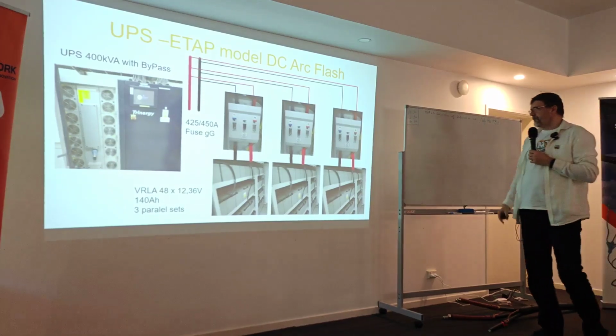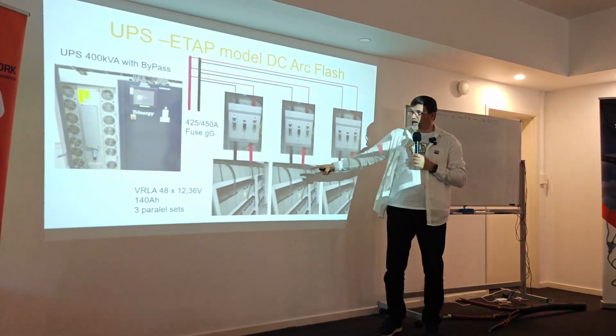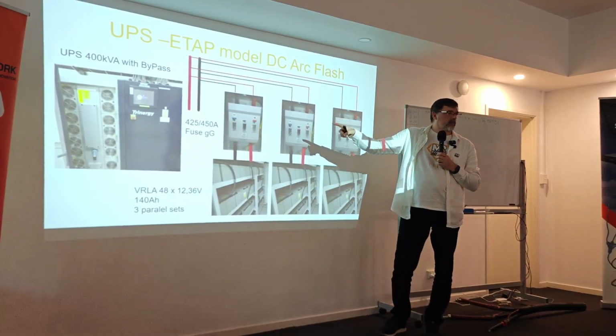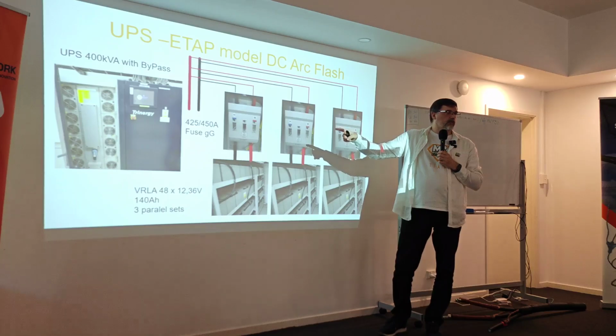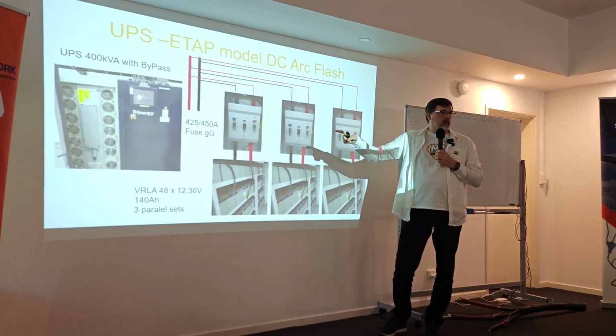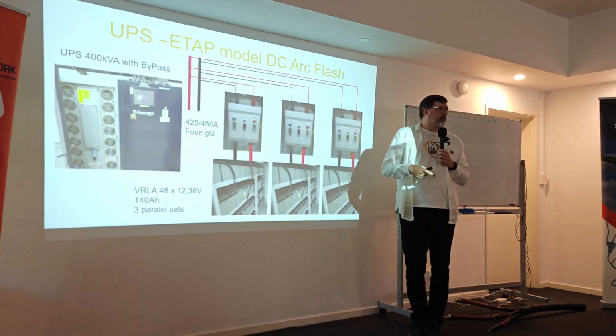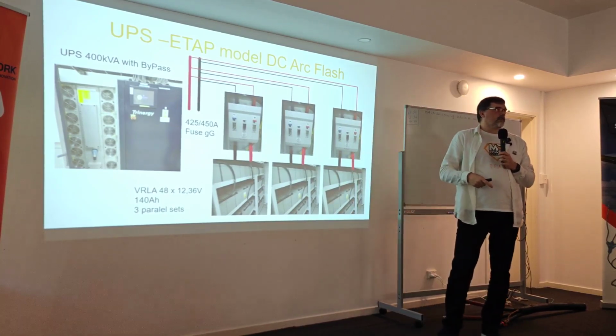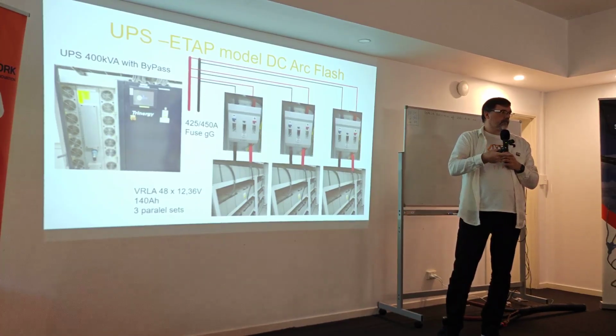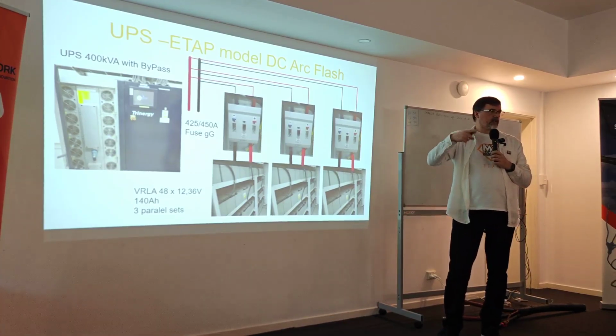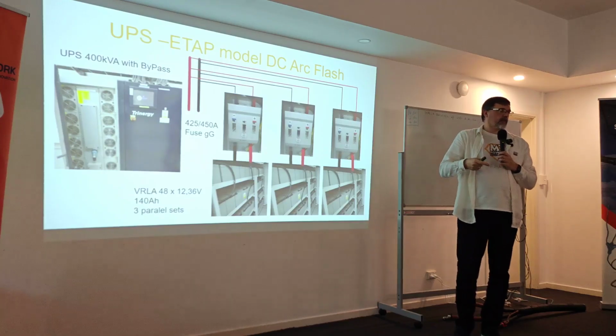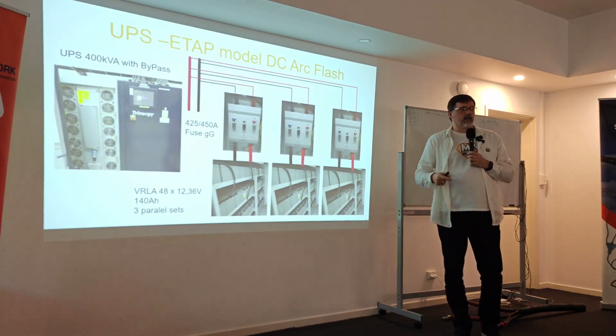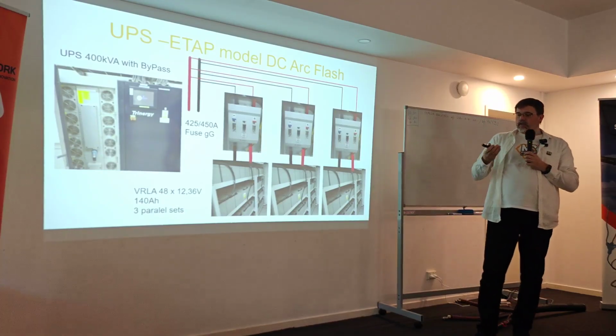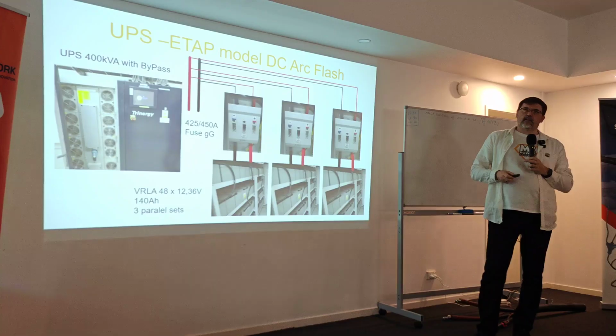So that was one of the cases that we have on one factory. There was actually factory support. Interesting thing, I don't know if you know, it's something which is called dynamic rotary UPS, DRUPS, which is spinning. It's something like the, what's the name in English? There are synchronous motors used in the grid to support the frequency. As a frequency support, like huge ones, like 200 megawatts and so on. So they just keep spinning, and when something happens, they're like, "Ooh, yeah, we support this frequency for a moment." Flywheel. Yeah, but the flywheel is the DRUPS, is the rotary UPS, and the synchronous.